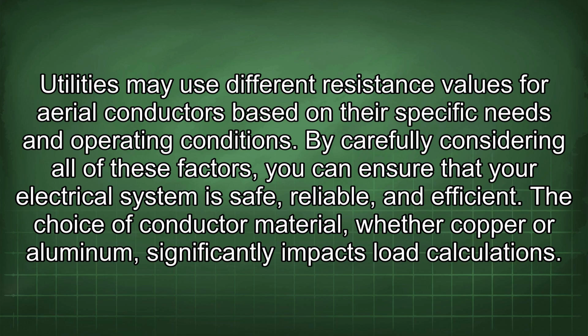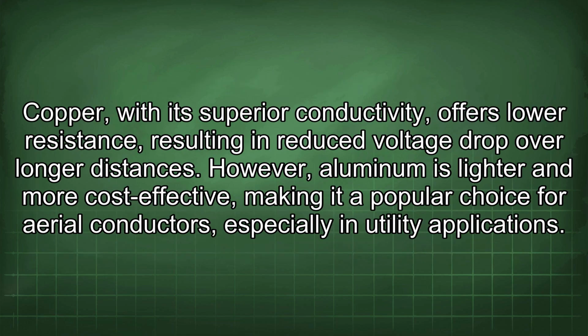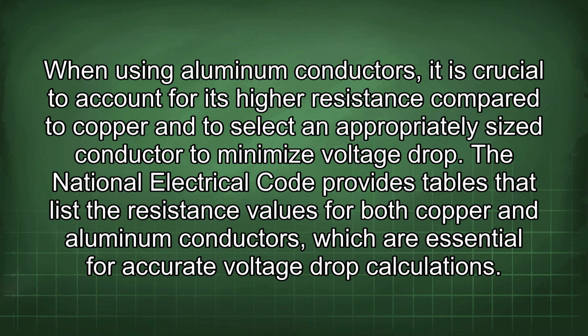The choice of conductor material, whether copper or aluminum, significantly impacts load calculations. Copper, with its superior conductivity, offers lower resistance, resulting in reduced voltage drop over longer distances. However, aluminum is lighter and more cost-effective, making it a popular choice for aerial conductors, especially in utility applications. When using aluminum conductors, it is crucial to account for its higher resistance compared to copper and to select an appropriately sized conductor to minimize voltage drop.